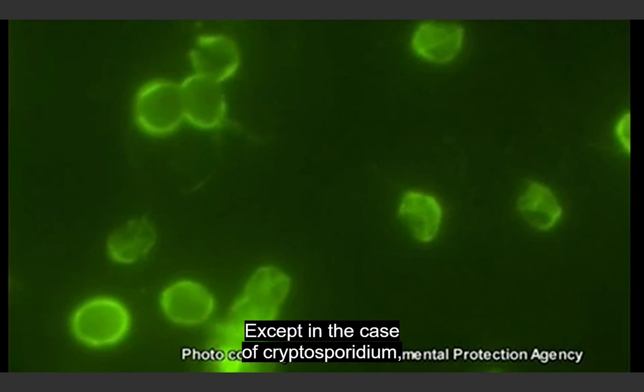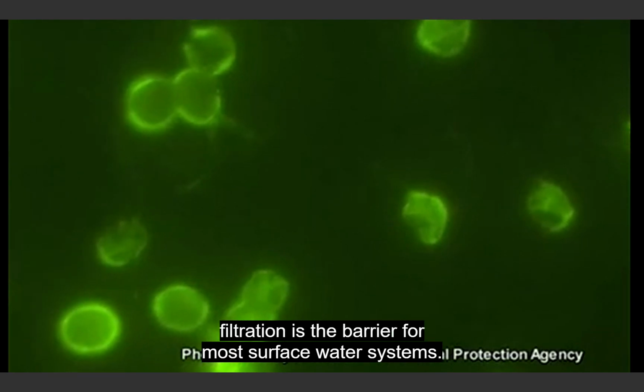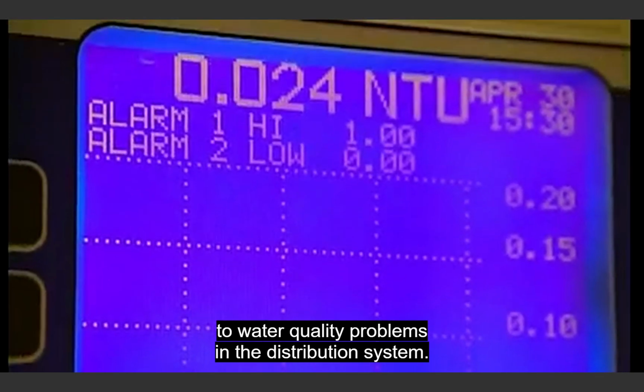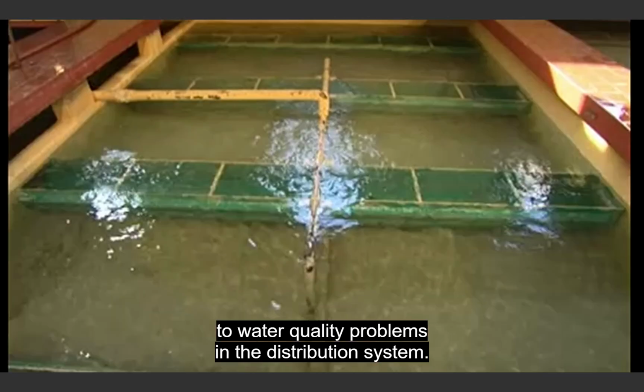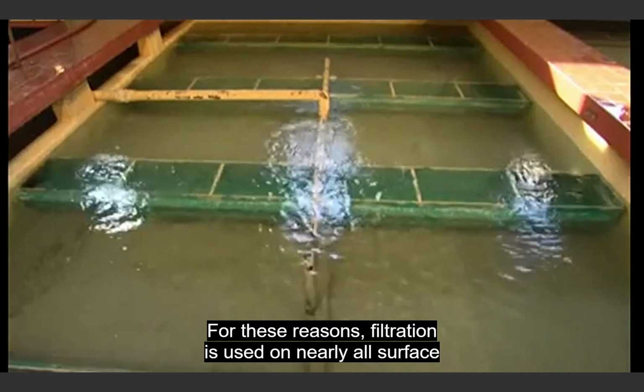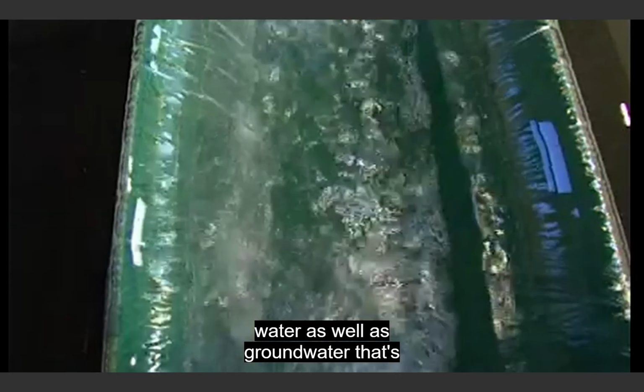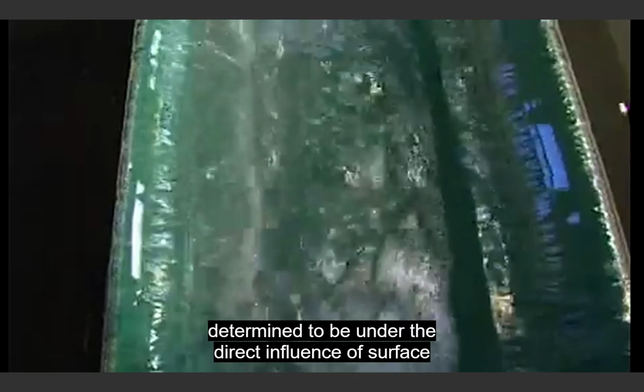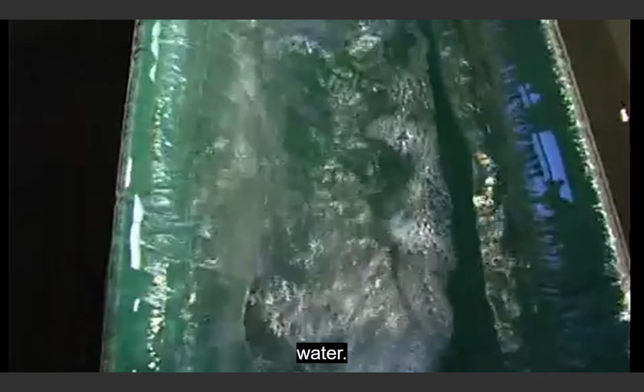Except in the case of cryptosporidium, filtration is the barrier for most surface water systems. High turbidity can also contribute to water quality problems in the distribution system. For these reasons, filtration is used on nearly all surface water, as well as groundwater that's determined to be under the direct influence of surface water.